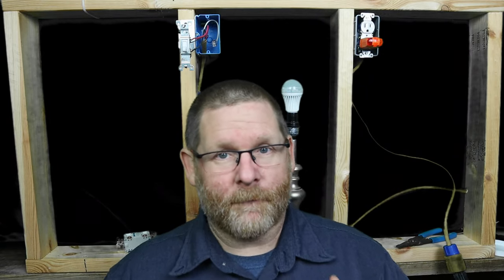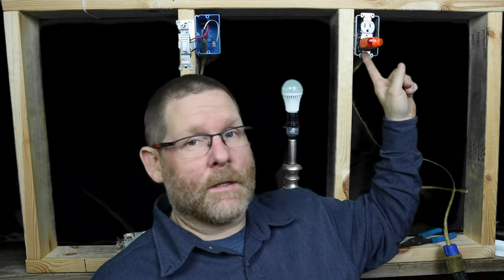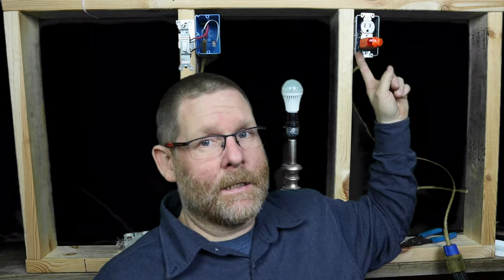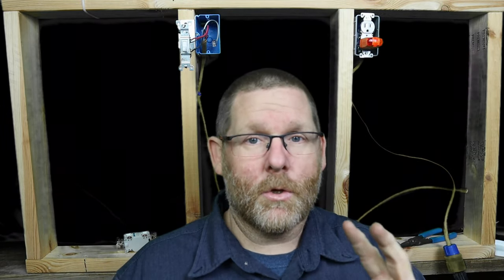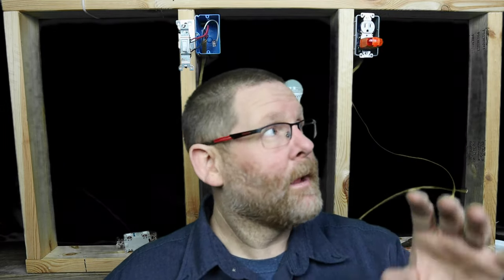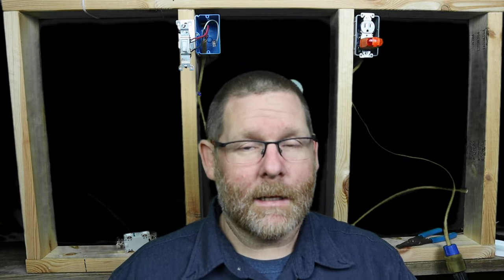I want to show you what not to do ever. All right, first of all, if you don't have a ground in this box, you cannot legally do, you cannot put a duplex on there, but you can put a GFI in its place. That will satisfy the code and make this safe.